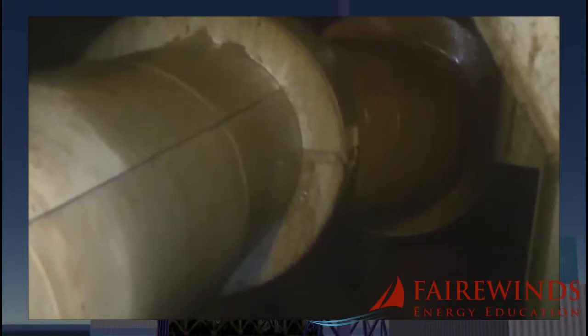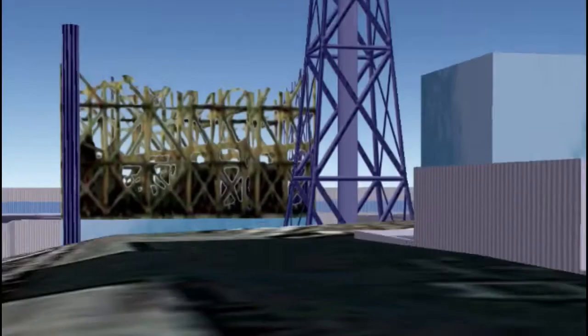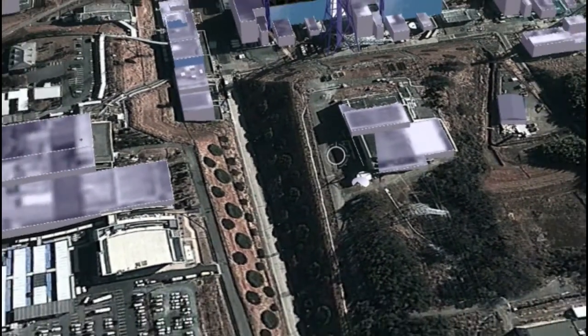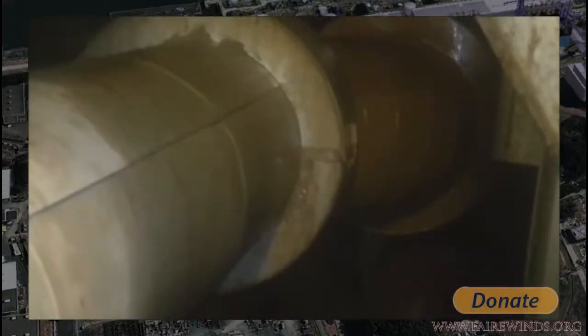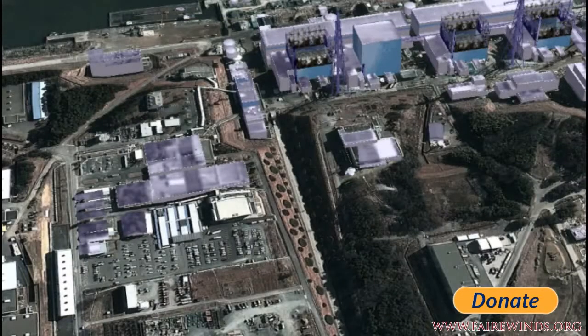The high area has a lot of groundwater, and water flows downhill — right into the basements of these power plants. The decision to cut away the bank, made in 1965 by General Electric and Ebasco, is the fundamental problem on this site because it's causing the basements to flood. Back in the 1960s, there was a large steep drop off to the ocean that was leveled by engineers.